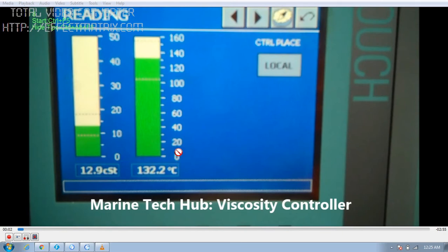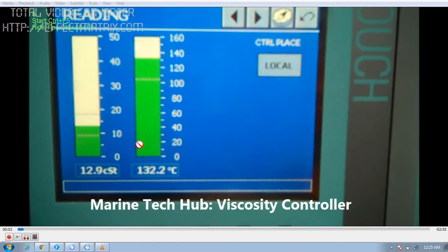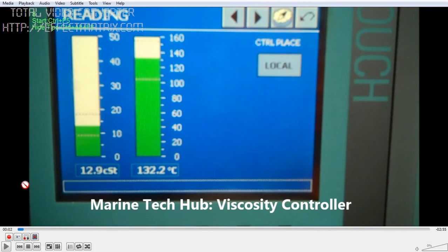I will be explaining you what to do when the viscosity sensor fails. You can use the temperature sensor to control the temperature to maintain the viscosity, since the viscosity sensor will not show any reading. So as per the bunker data you will be able to know at what temperature the viscosity will be 13 centistoke. We maintain the temperature here. In case both viscosity control and temperature control are not working, you can always open the steam manually and check the local panel.